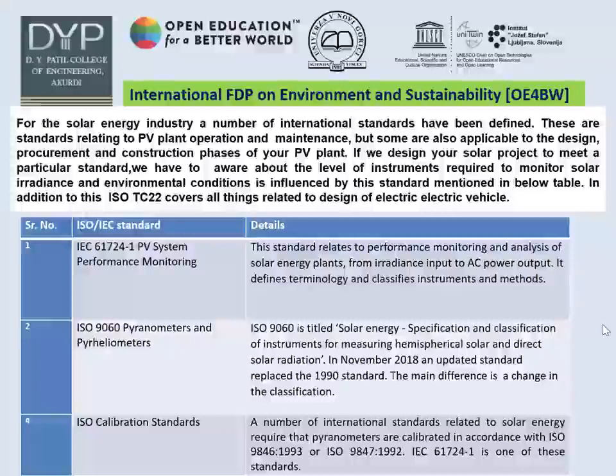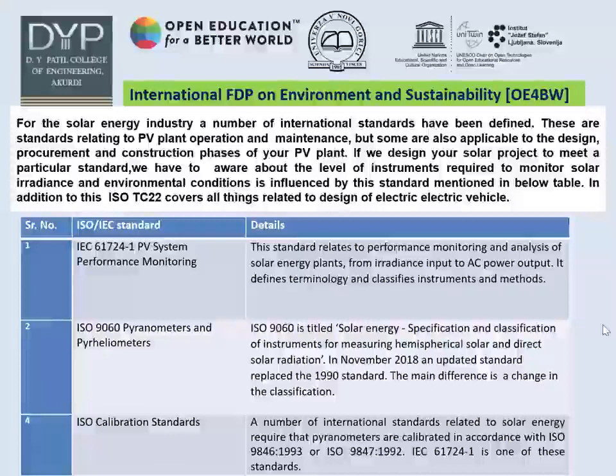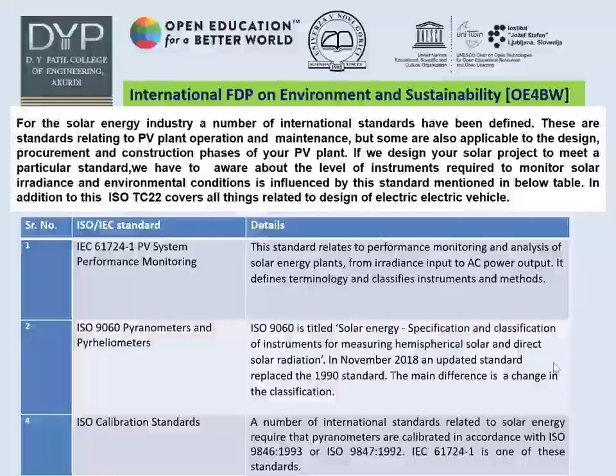IEC 61724-1 defines terminologies and classifies instruments and methods. ISO 9060 is titled Solar Energy — Specification and Classification of Instruments for Measuring Hemispherical Solar and Direct Solar Radiation. In November 2018, an updated standard replaced the 1990 standard, with the main difference being a change in classification. A number of international standards related to solar energy require that pyranometers are calibrated in accordance with ISO 9846:1993 or ISO 9847:1992. IEC 61724-1 is one of these standards. These standards give an overview of solar systems and solar electric panels.